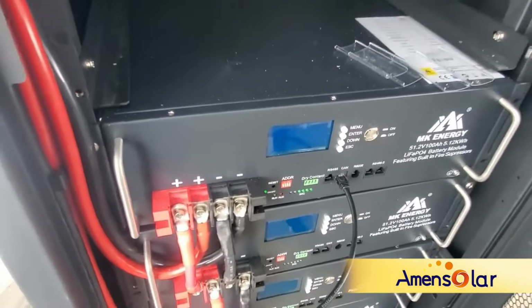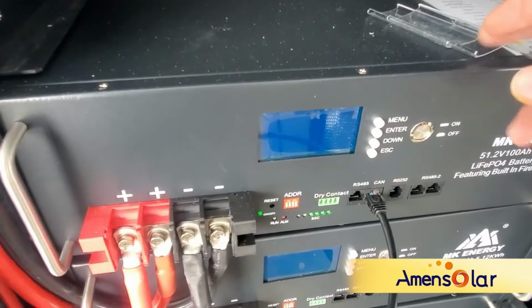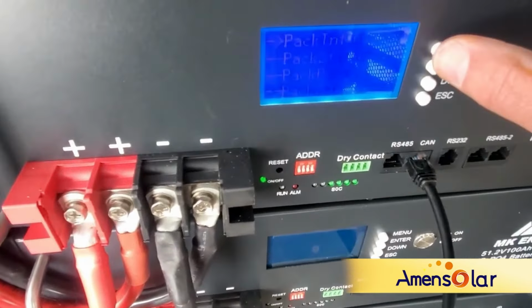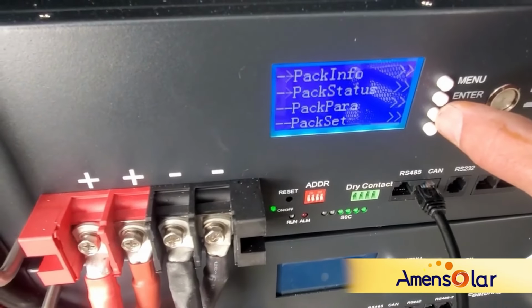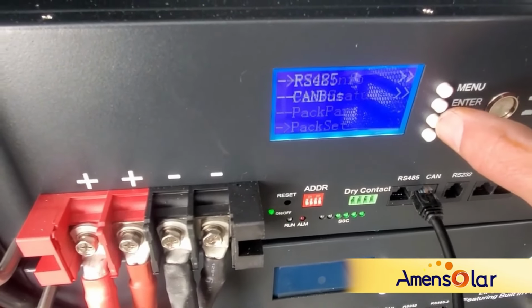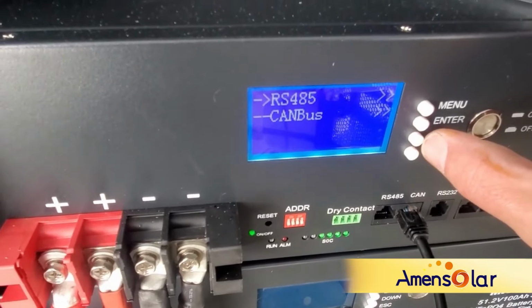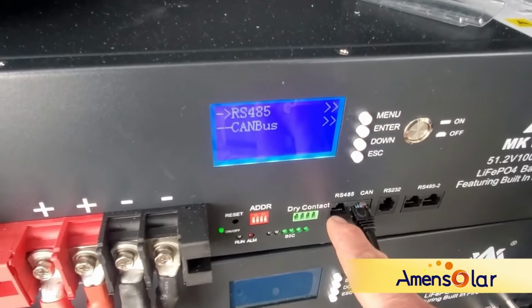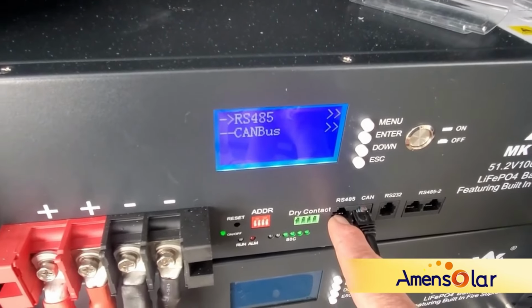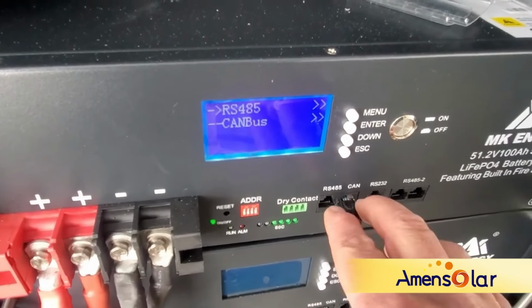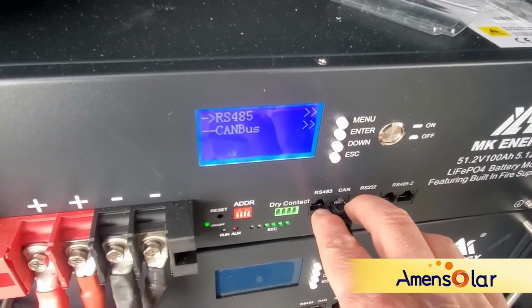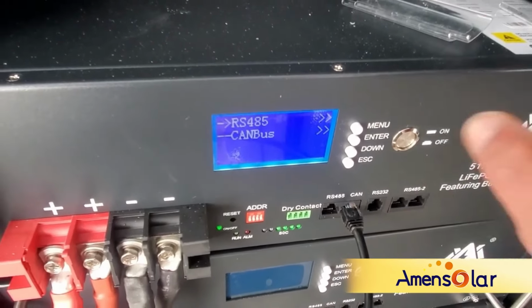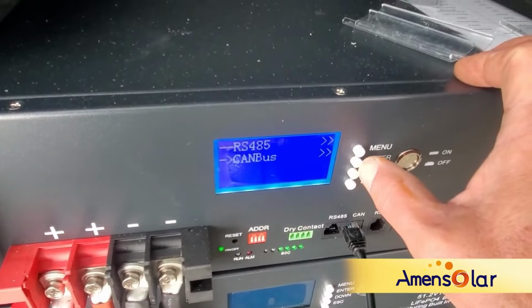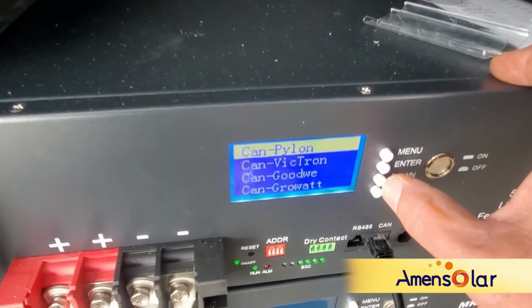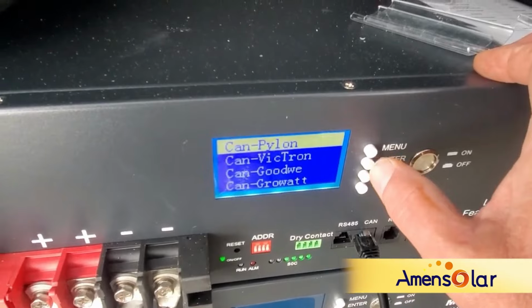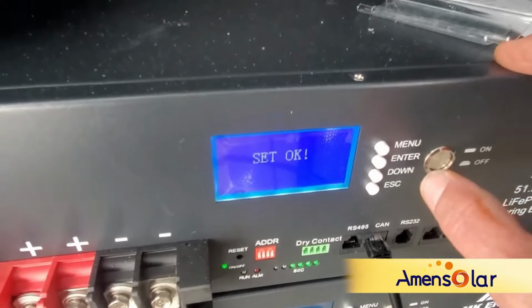What's cool about these batteries is you can program the protocols right there. What's cool is you can actually run an inverter off the RS485 port on a different protocol than on the CAN port, so you can have two separate inverters reading different protocols running off different ports on these batteries. So we're going to set it to CAN bus, and Pylon Tech works just great. We push enter, and it says set OK.